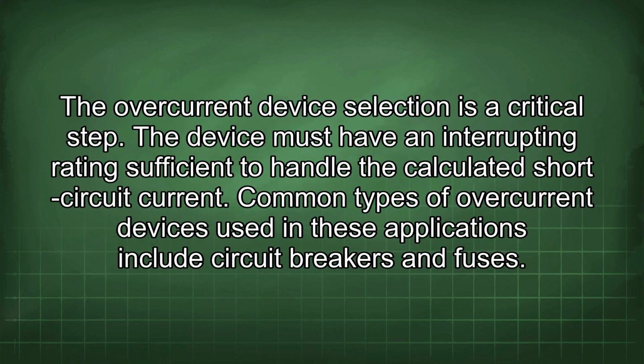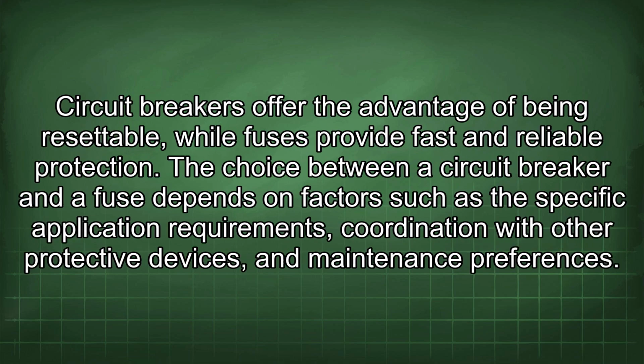The overcurrent device selection is a critical step. The device must have an interrupting rating sufficient to handle the calculated short-circuit current. Common types of overcurrent devices used in these applications include circuit breakers and fuses. Circuit breakers offer the advantage of being resettable, while fuses provide fast and reliable protection. The choice between a circuit breaker and a fuse depends on factors such as the specific application requirements, coordination with other protective devices, and maintenance preferences.